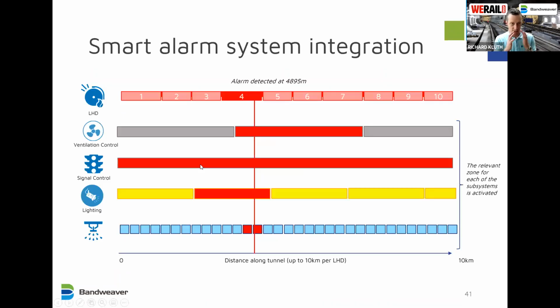So if we look at the schematic of an example of some different zones within a system, what we see is, on this axis on the bottom, the length along the tunnel, and then these are each of the different systems: linear heat detection, ventilation control, signal control, lighting, and fire suppression. So the linear heat detection is divided into 10 zones, and that corresponds with the 10 zones designated in the fire control panel. The ventilation control would be decided by how many fans there are in the tunnel. In this case, there are 3 zones. Signals, how many signals? In this case, say just 1 signal per section, so it's a binary decision. And the lighting, 4 zones, fire suppression, many more zones.